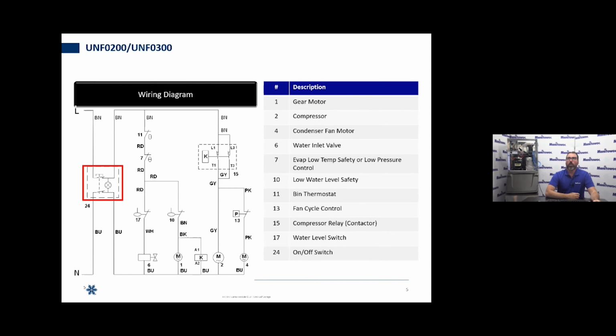On a UNF under counter 200 or 300 series, the unique thing about these is they don't use a timer. There's no time delay like you would see on some of our larger models. It's just a simple on-off switch and a few different safeties. We're going to have a bin thermostat safety. We're going to have evap low temp, so we want to make sure that we don't freeze that evap up. So we're going to have a low temp pressure safety.